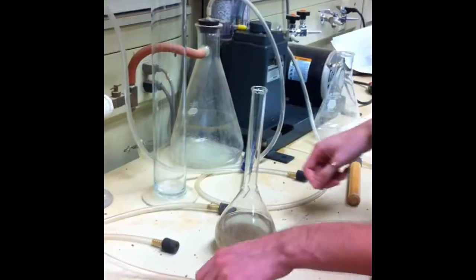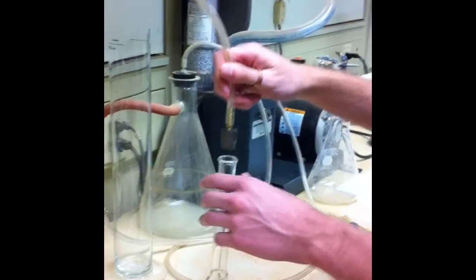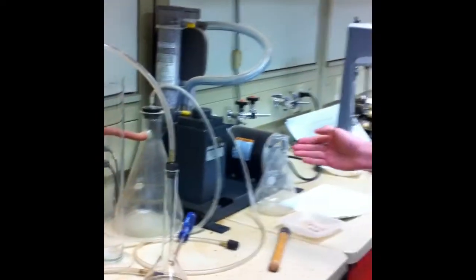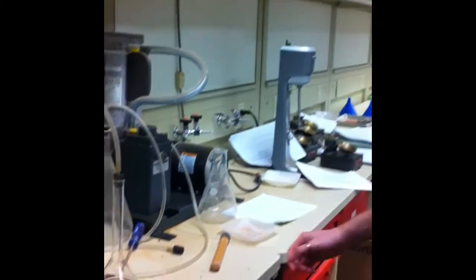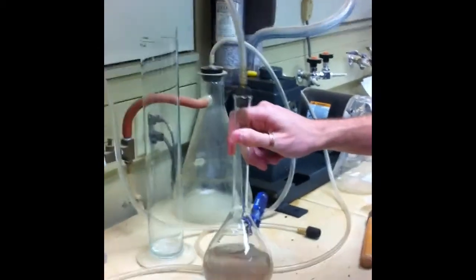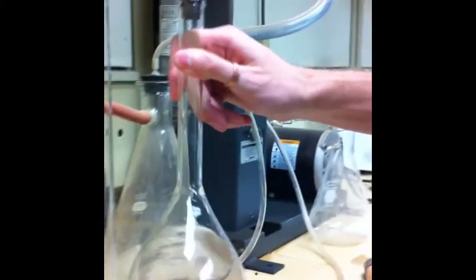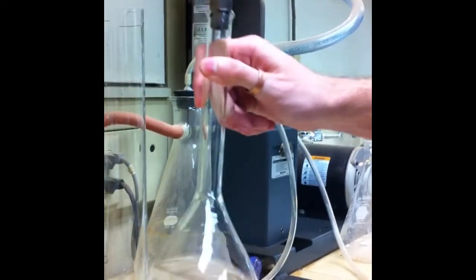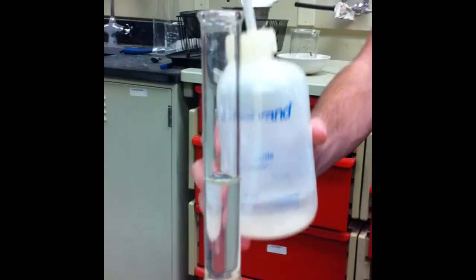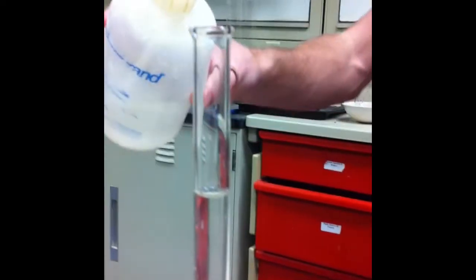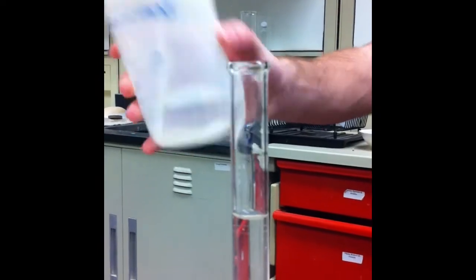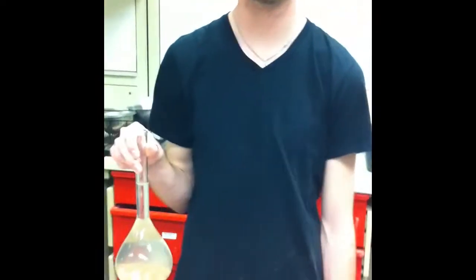It is time to deair the sample. Attach it to the deaeration device properly, open the valve, and turn the deaeration device on. For the purpose of this experiment, we let the machine run for 1 minute with constant agitation over 5 cycles. In the ASTM, you are instructed to do so for 30 minutes. Now, fill the water pycnometer up to the nominal fill line precisely once again.